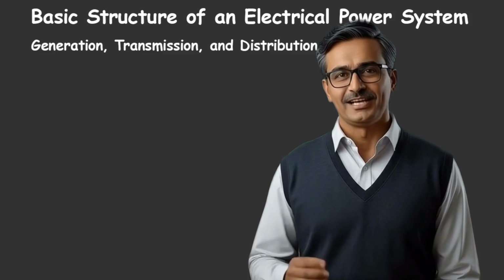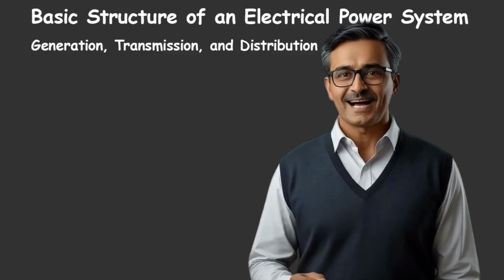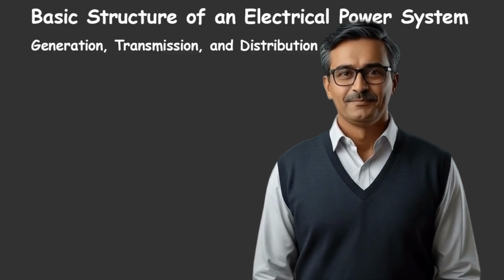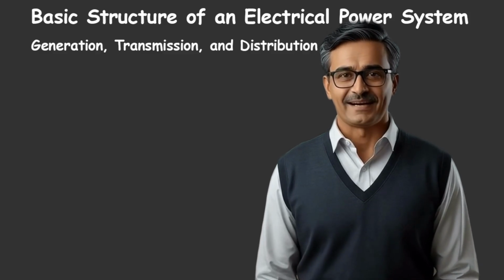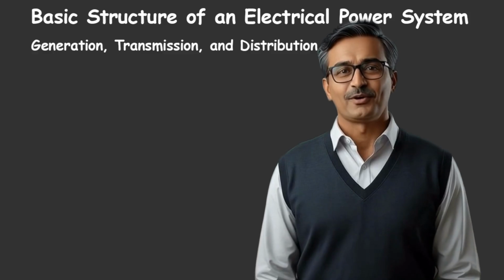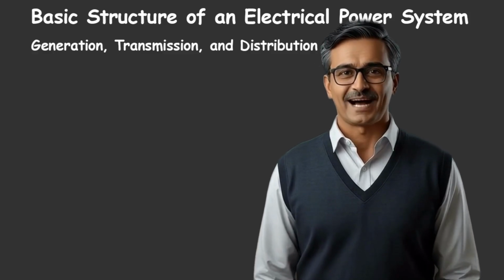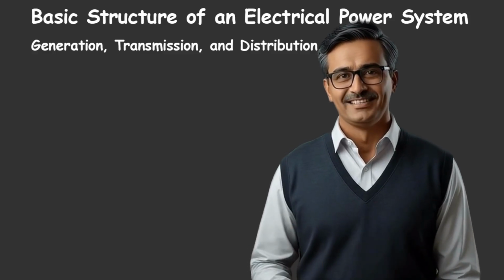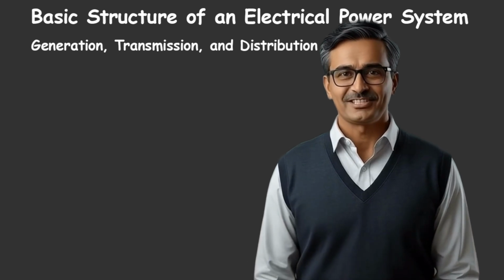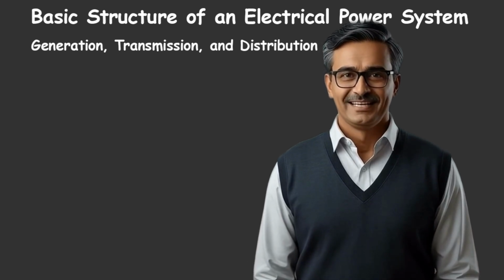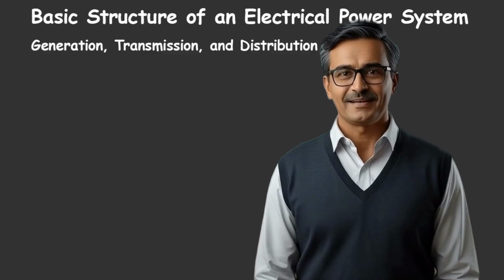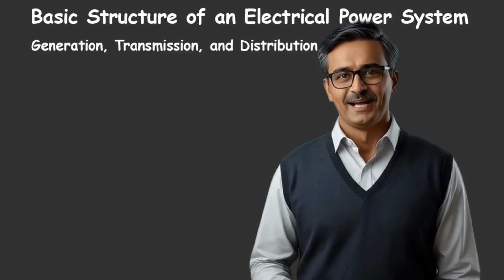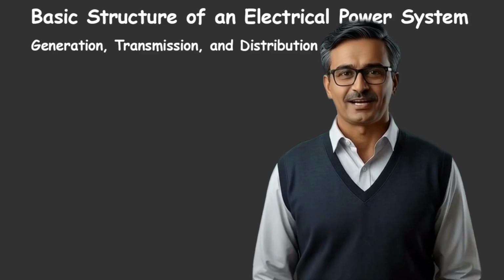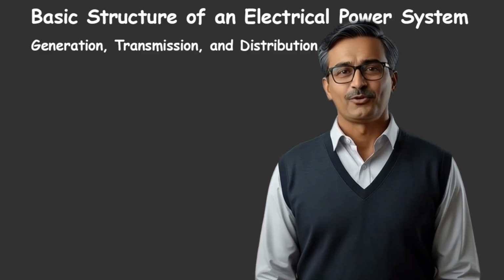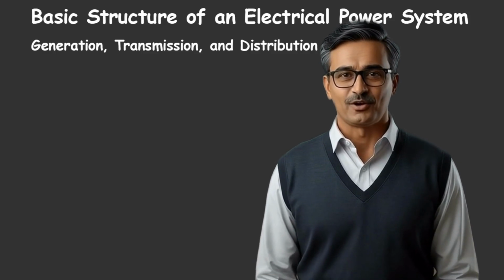But at the distribution end, we cannot directly supply this high voltage power to our homes. In our homes, we need 220 volts for single-phase supply or 415 volts for three-phase supply. So this high voltage power is stepped down in sub-transmission and distribution substations. Ultimately, it is stepped down to 11 kilovolts, and then this 11 kilovolt supply is further converted to 415 volts or 220 volts by distribution transformers.